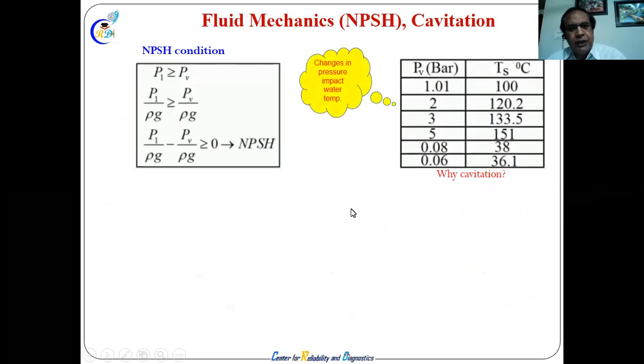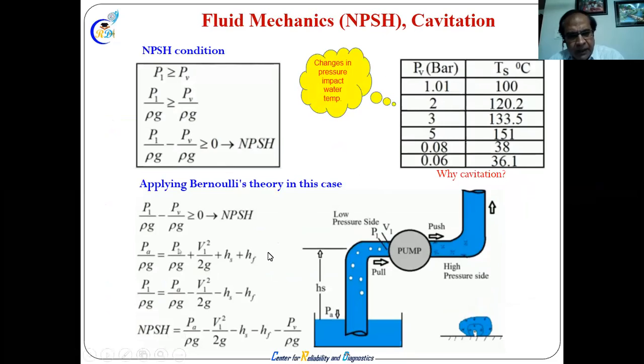And all this formula takes care of the Bernoulli equation and how it becomes; this Bernoulli equation is applicable here. The ultimate aim is available suction head. I'm not going to discuss it here because we are not discussing only pumps, so we will not go into details. But you see, if the pressure carries on decreasing, vapor pressure carries on decreasing, then your temperature is decreasing, 36. So 36 degrees, can you touch it? Okay, you can touch it, but at 36 degrees you cannot go around Mumbai, it is so hot. So if a change in pressure impacts water temperature, that creates cavitation, and this creation is here and nearby. So we have to take care that the inlet pressure is always higher than your vapor pressure. So vapor pressure should not go down like this. That's what the formula tells.